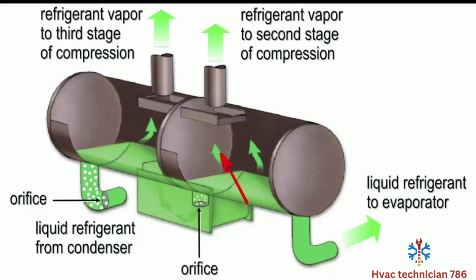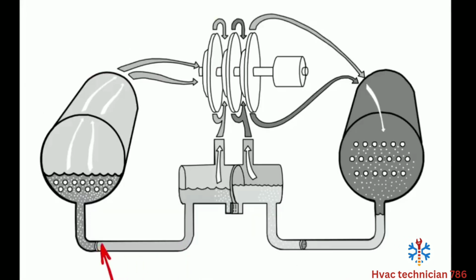And by doing this, we further reduce the total work the compressor has to do, and by returning the suction gas back into the compressor at a medium pressure state, it has to do less lift to increase it to a condensing pressure. And then we will leave the economizer back to the evaporator, where we will have our final stage of flash, and then we enter the evaporator.